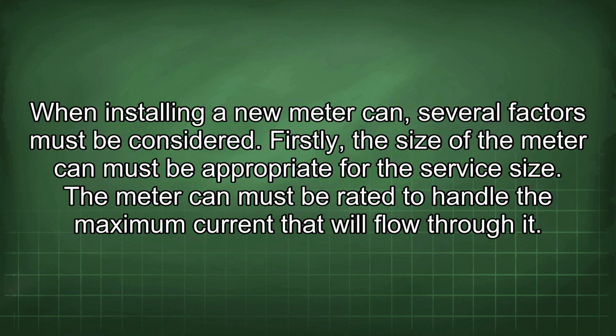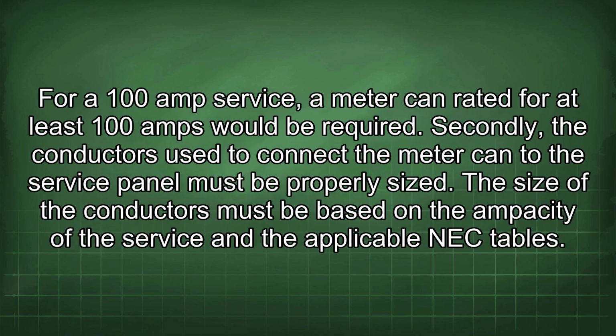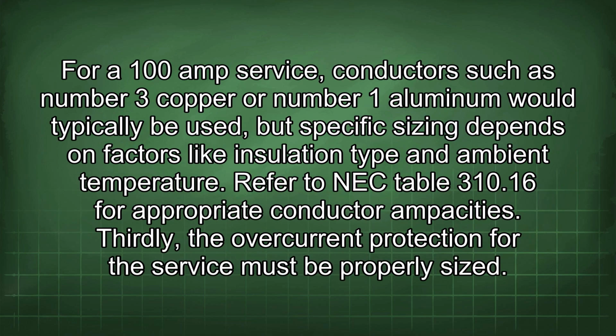Firstly, the size of the meter can must be appropriate for the service size. The meter can must be rated to handle the maximum current that will flow through it. For a 100 amp service, a meter can rated for at least 100 amps would be required. Secondly, the conductors used to connect the meter can to the service panel must be properly sized. The size of the conductors must be based on the ampacity of the service and the applicable NEC tables. For a 100 amp service, conductors such as number 3 copper or number 1 aluminum would typically be used, but specific sizing depends on factors like insulation type and ambient temperature. Refer to NEC Table 310.16 for appropriate conductor ampacities.